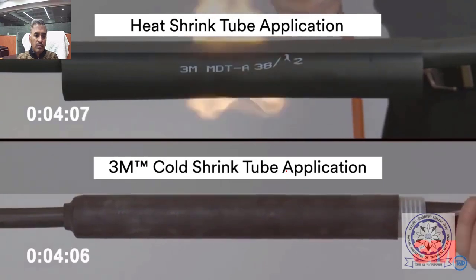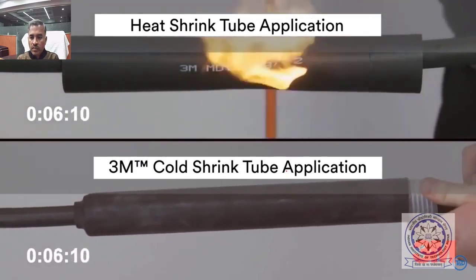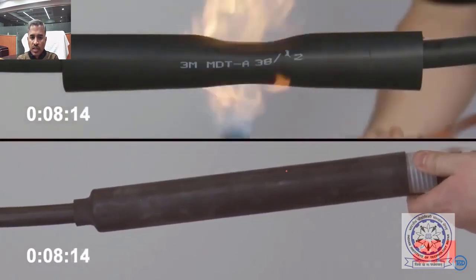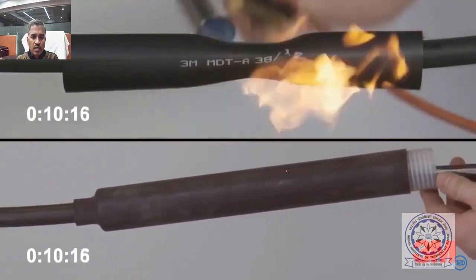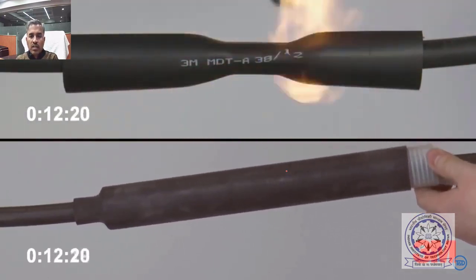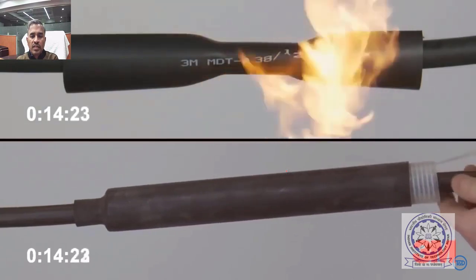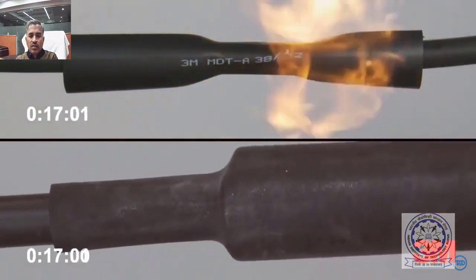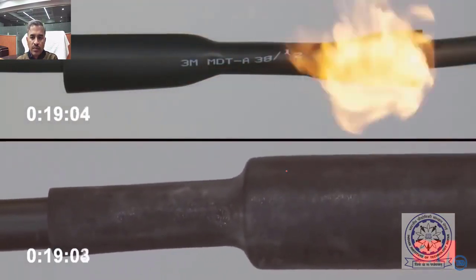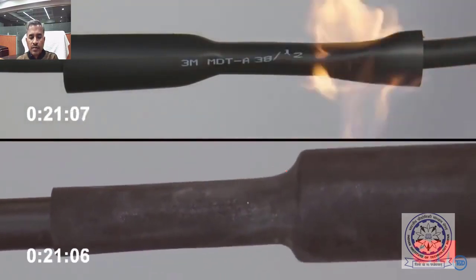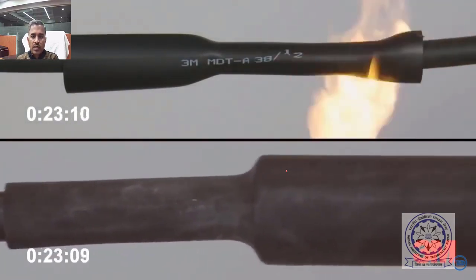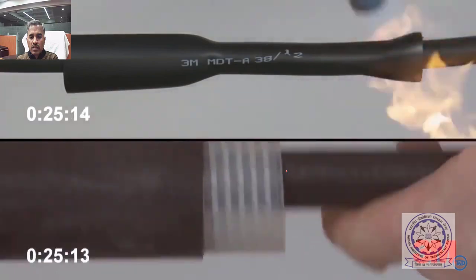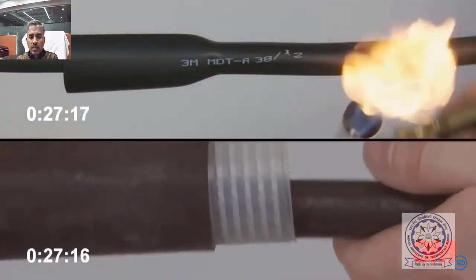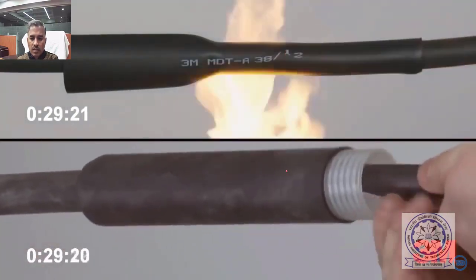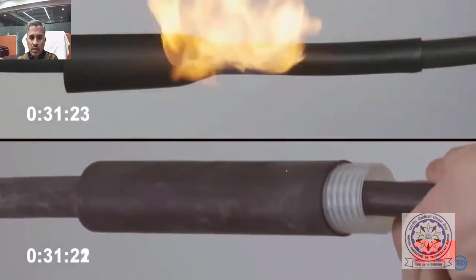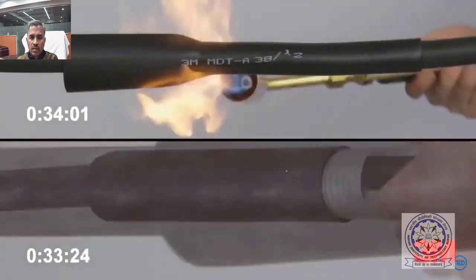3M invented cold shrink technology over 30 years ago. Cold shrink, our cold apply products utilize the unique cold shrink delivery system designed to make cable jointing, insulating, termination and abandonment as simple as possible. Compared to heat shrink alternative, there is less chance of damaging XLP cable material, less room for jointer error and no cooling time needed before energizing. It is easier to use in closed areas and there is no requirement for special site permits.